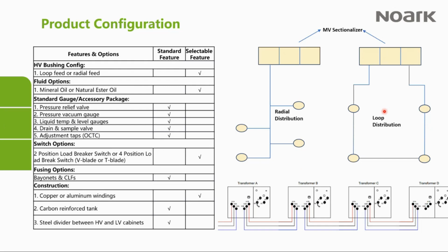So again, this is more common around the cities, in built up areas, residential areas, because what this does is that it gives you reliability, because you can actually have a second supply. Sometimes you could have faults happening, for example, in the radial distribution. If you have a fault along this line, it means that everybody that is being serviced by this line is out of power. But in the case of a loop distribution, if you have a fault along this line, you can simply feed again from this end to all the customers without them losing availability. So that's the importance of the loop type of distribution.